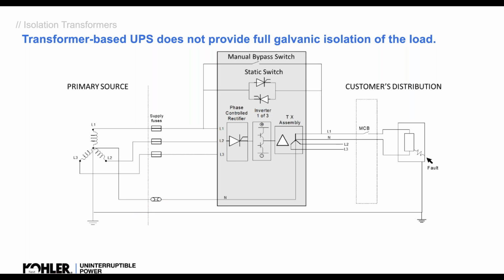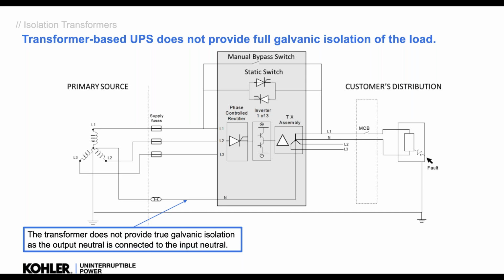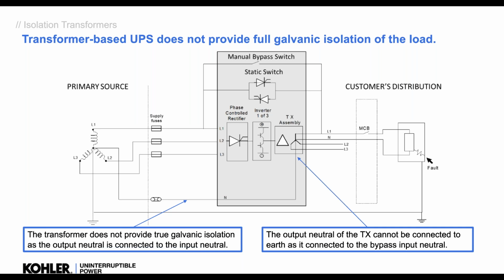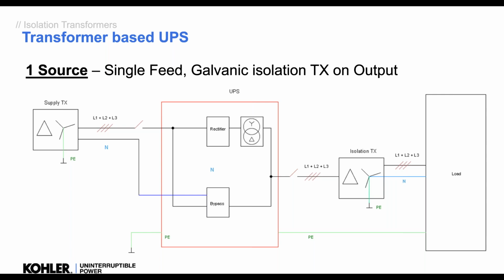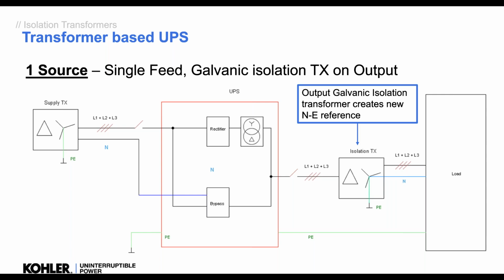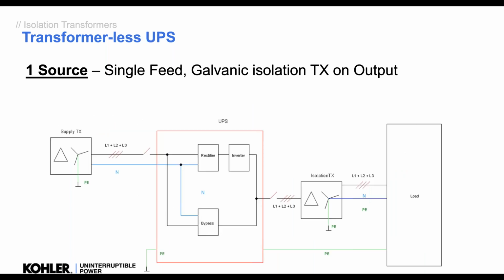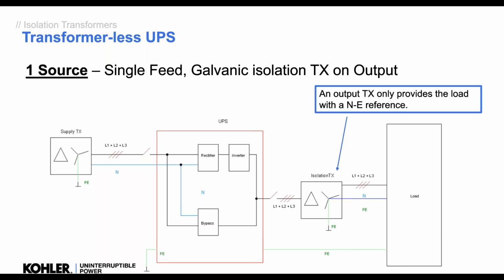So it doesn't matter what type of UPS we have, it does not create the new neutral earth. If it's a transformer or transformerless, we still need that output transformer to create a new neutral earth. Okay, so we have to put a transformer, ideally as it says, on the output. Three-phase in, typically a delta star transformer, and we re-earth the neutral on the output to create a permanent neutral to the load, so we never lose that neutral earth on the load. Okay, so this is an old transformer-based UPS, and a modern one would be very much the same here. So we've got no transformer here, but we have to put one on the output. Okay, so it doesn't matter if it's transformer or transformerless, you need an isolation transformer to re-earth that neutral supply.